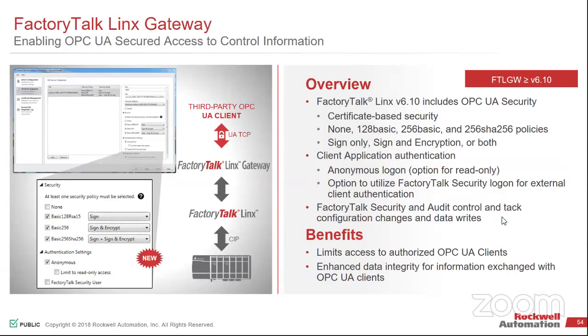Yeah, because at that point, if we needed to go faster, we still have the Softing option, the third party, and that's a hardware-based solution. That might be something if we needed to do OPC UA at, let's say, 50 milliseconds, I think we would go down that route. But if we needed to do something at a standard Windows rate that we're able to pull from the HMI side of it, we end up using this.